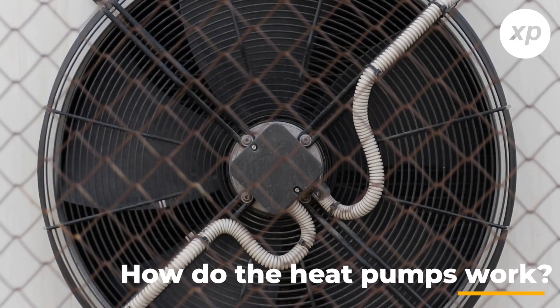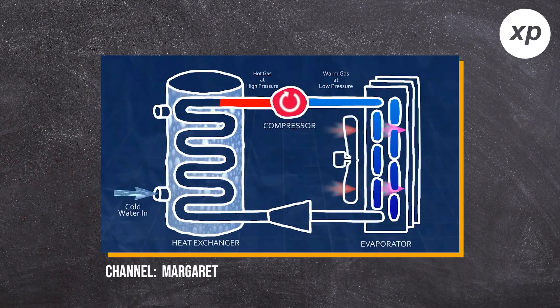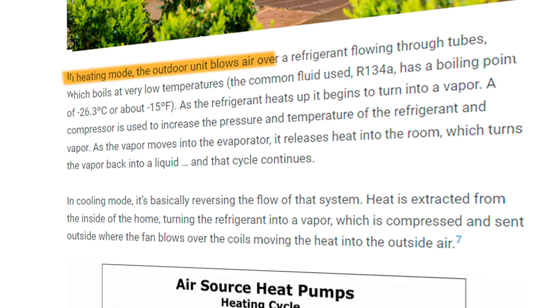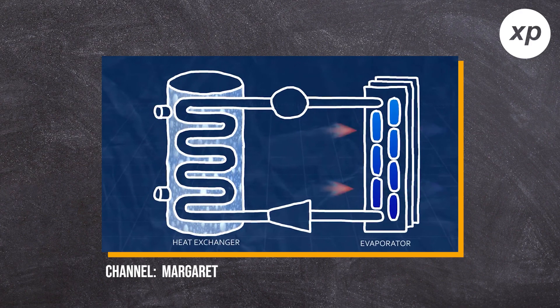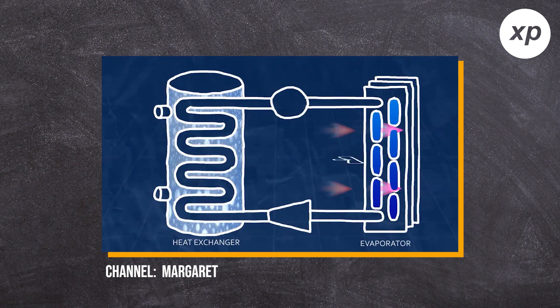To start off, a heat pump is very similar to our common air conditioning system. They refer to it as an air-to-air pump. For these air-to-air pumps to be able to cool and heat, it needs a reversing valve. In heating mode, the outdoor unit blows air over a refrigerant flowing through tubes, which boils at a very low temperature. As the refrigerant heats up, it begins to turn to vapor. A compressor is used to increase the pressure and temperature of the refrigerant and vapor. As the vapor moves into the evaporator, it releases heat into the room, which turns the vapor back into a liquid, and that cycle continues. The way it cools is basically the reverse of this process — heat is taken from the inside of the home, turning into vapor, which is compressed and sent outside.